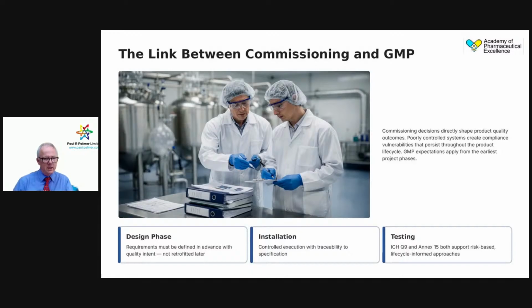The link between commissioning and good manufacturing practice. Design phase: define what the expectation is in advance, not after the event. Installation, traceability, and testing, of course. But commissioning decisions will directly impact product quality outcomes. Poorly controlled systems will result in compliance issues and vulnerabilities.